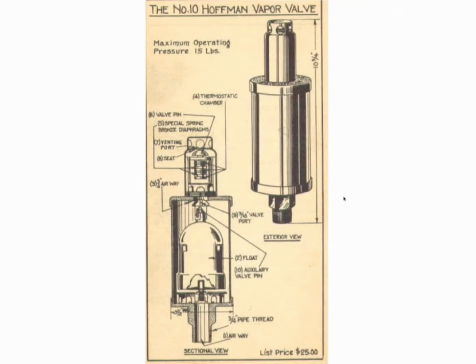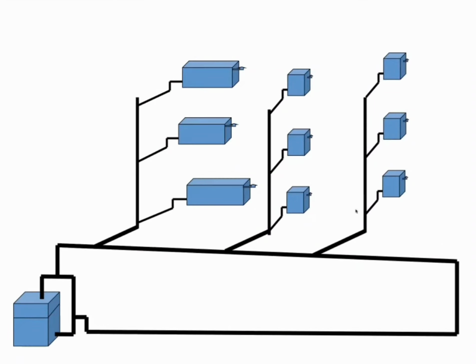Because those automatic fuels change things dramatically. Here's what I mean. When you start up a boiler, the steam's going to form. We're going to have an air vent down the end here, and they might put that Hoffman number 10 down there. And when the steam starts up, we want the steam to move through the header, out into the system, and down that line. Now, there was a system developed by the oil guys in the 1930s that they called master venting.